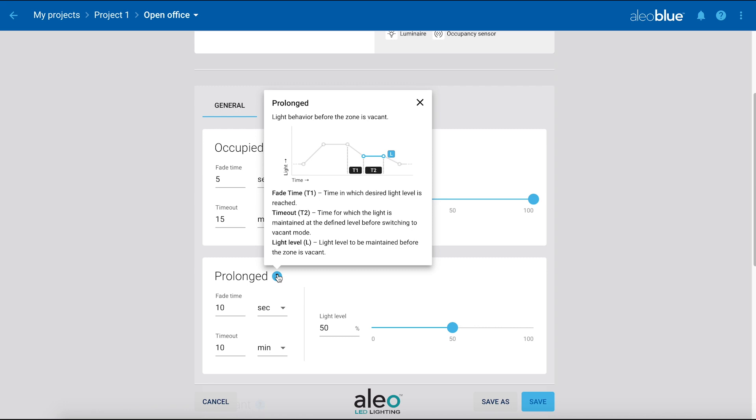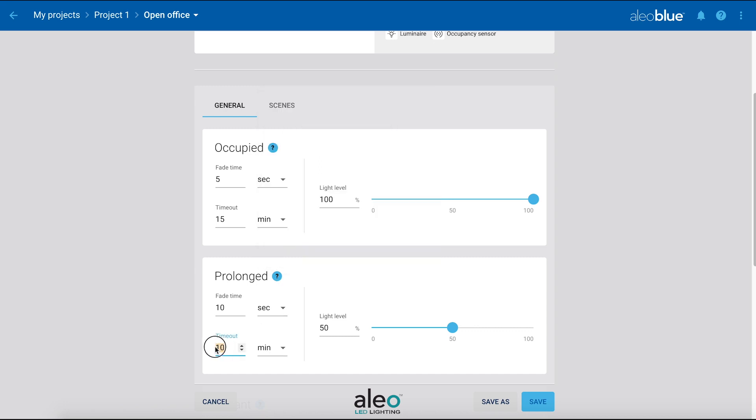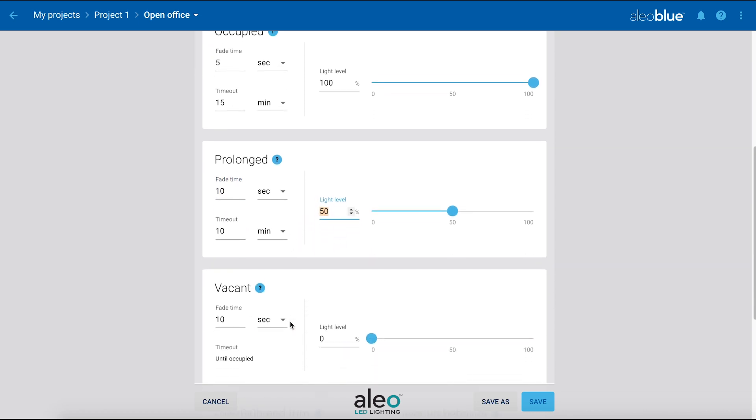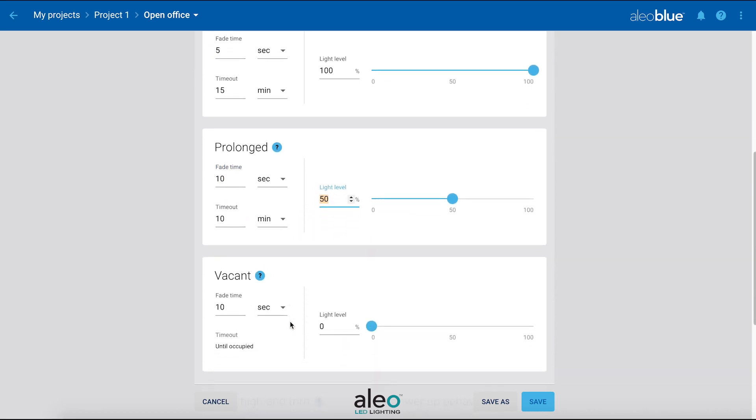Prolonged is the secondary light level once occupancy is not detected. We will be setting that time delay to 10 minutes and a fade time to 10 seconds at a 50% light level. Once motion is not detected for 10 minutes, the light will dim to the vacant level.